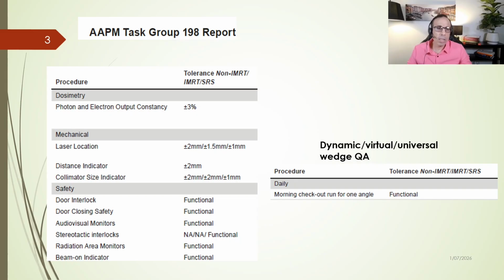Now, let's look at this table. This summary comes directly from the AAPM TG198 report, which is our official guide for checking medical Linacs. The entire daily QA can be broadly divided into three key components: dosimetric, mechanical, and safety checks. Together, these tests provide confidence that the Linac is ready for safe clinical use before the first patient is treated.